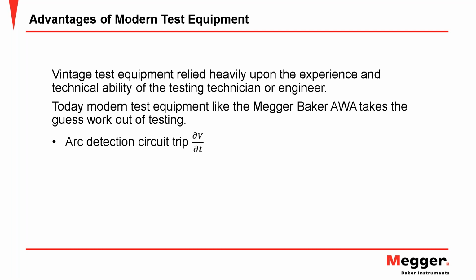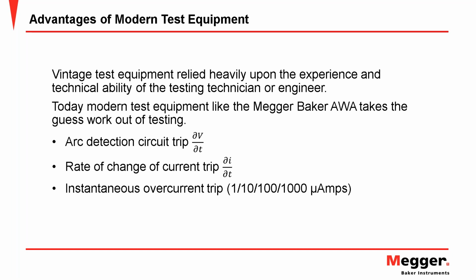Again, we have arc detection circuits that look for instantaneous changes in voltage and immediately stop the test to limit the current. Of course, if the current changes a little more slowly, but the rate of change of current starts to increase, we can also stop the testing there. And of course, we have instantaneous overcurrent trips at several levels that can mitigate the level of current that's going to cause carbonization, if you will, of the insulation.